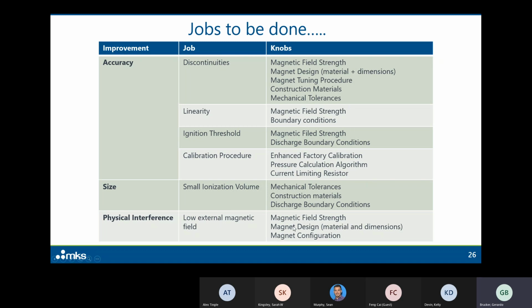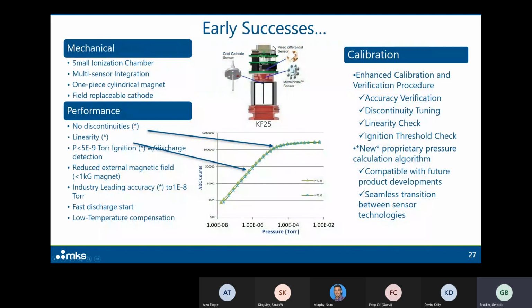So there were a lot of variables that we had to tweak in order to get to the cold cathode gauge design that would provide all the features that we were looking for. This is a very long laundry list of things that you have to look at when you're doing R&D in a lab, so I'm obviously not going to go through all of them. We don't have time. But early on, even with the early prototypes, we had a lot of early successes. From the mechanical point of view, we were able to make a small ionization chamber. We were able to do the multi-sensor integration. We were able to do all this with a single piece cylindrical magnet, and including a field replaceable cathode in the device.